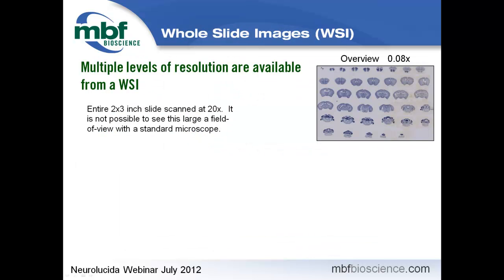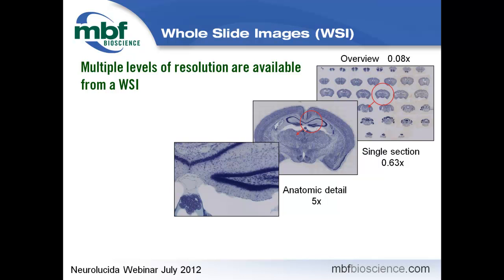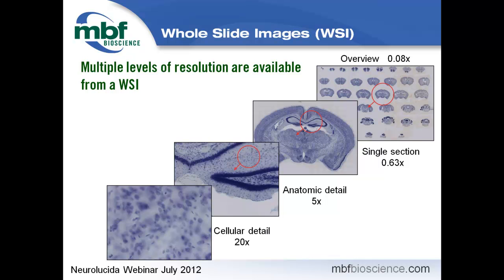We also have a product line that handles whole slide imaging, what we call virtual slides — our virtual tissue line. You take an entire slide and digitize it at high magnification: 40, 60, or 100x. That slide is made up of thousands of different image planes, all stitched and merged together into a single image at multiple resolutions. You can zoom from the whole slide image down to anatomical detail at 5x and then to the cellular level at 20x, performing analysis or reconstructions from a single whole slide image.